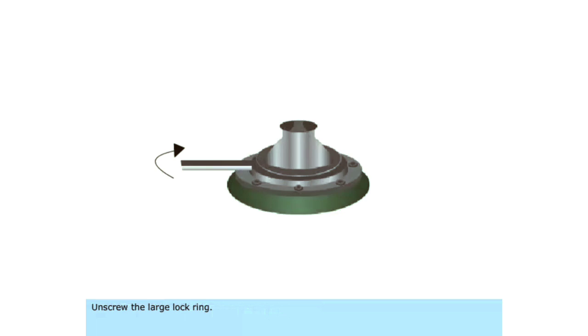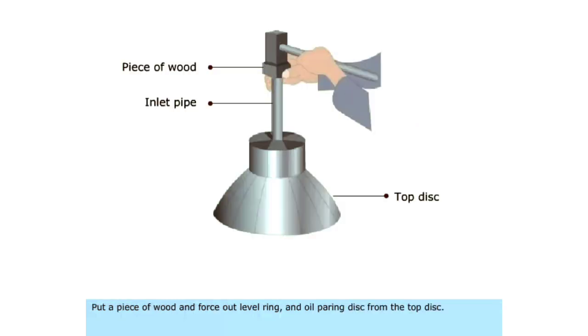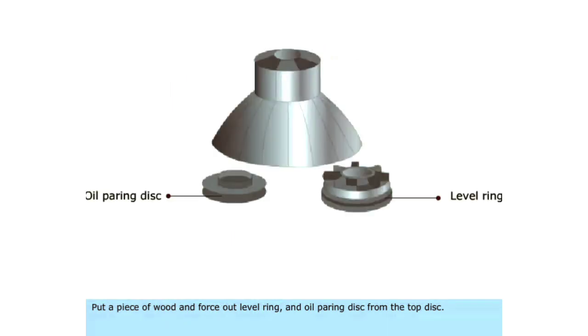Unscrew the large lock ring. Lift out the bowl hood by special lifting tool. Put a piece of wood and force out level ring and oil paring disc from the top disc.